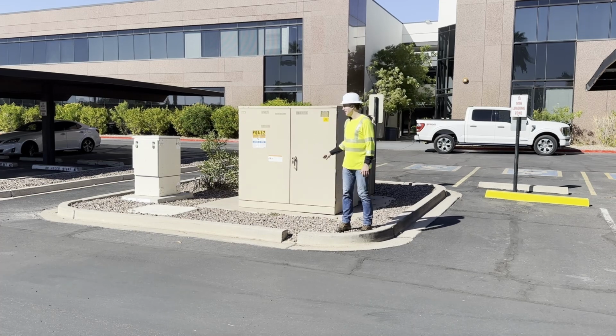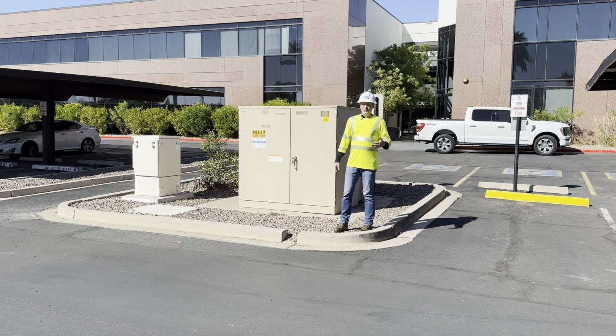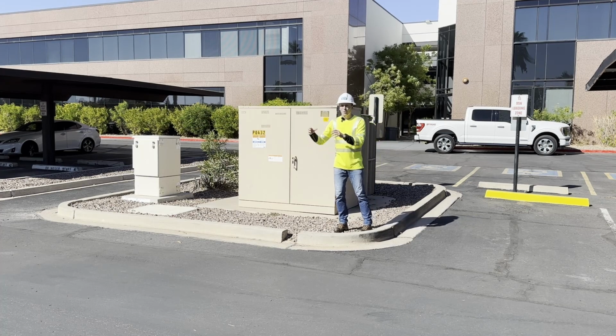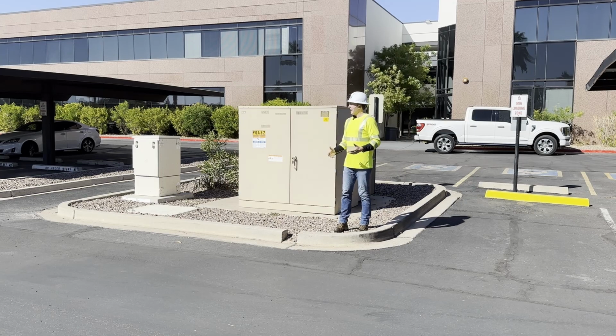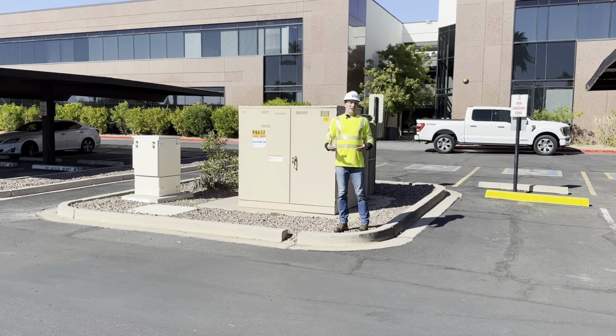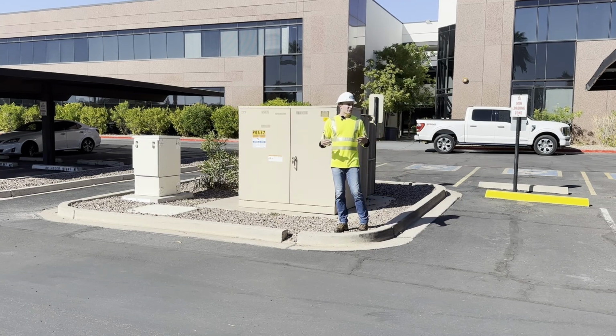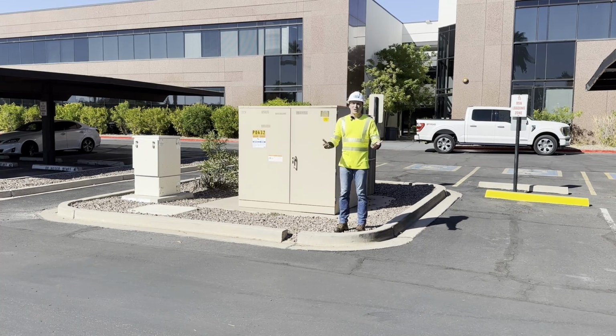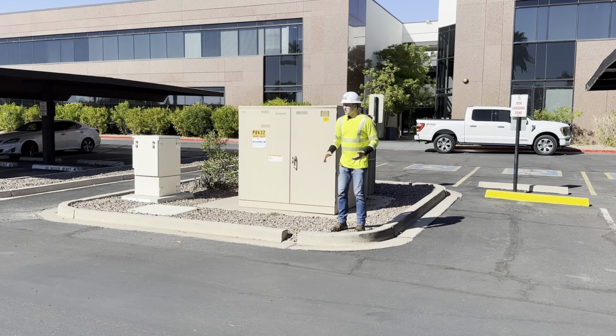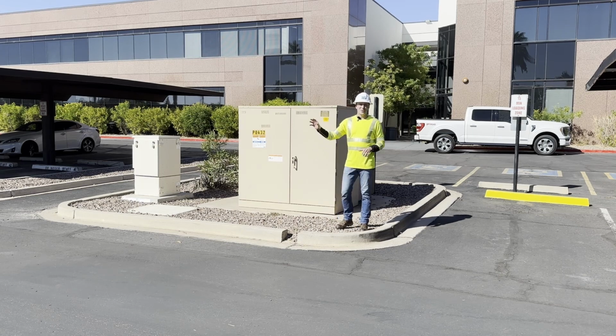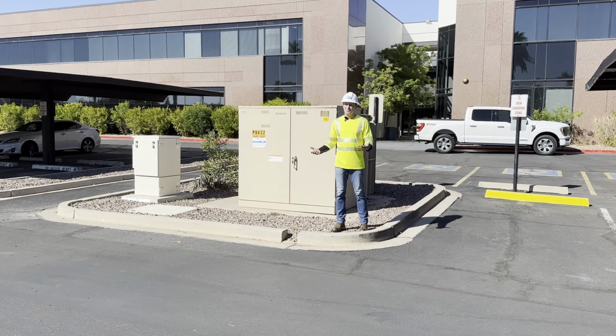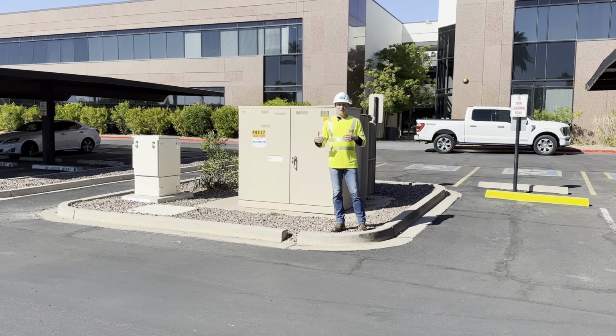Bad things will happen. So the electric service requirements from each utility will call out where and when they want bollards, but occasionally the utility might want bollards in areas or times you didn't expect, just because they're going to play on the safer side. And honestly, for EV charging projects, your transformer is probably going to be pretty close to where vehicles are parking, so it's always best practice to err on the side of caution and put those bollards.